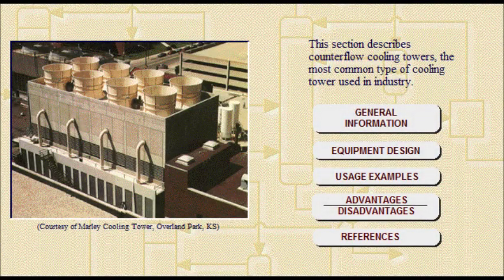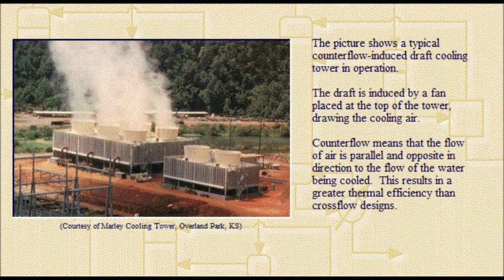Here we describe counter-flow cooling towers, the most common type of cooling tower used in industry. The picture shows a typical counter-flow induced draft cooling tower in operation. The draft is induced by a fan placed at the top of the tower drawing the cooling air. Counter-flow means the flow of air is parallel and opposite in direction to the flow of the water being cooled, resulting in a greater thermal efficiency than cross-flow designs.